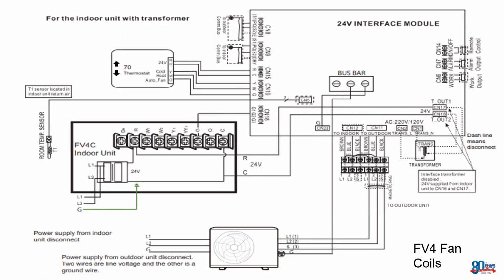Okay, so now what we want to look at is our third-party thermostat. Typically, we see our Ecobee thermostats, which we sell here at Standard Air Lite, but it could be any 5-wire non-heat pump thermostat. Okay, now you have your R and your C, your hot and your common, which is going to feed up to CN15 on the 24-volt interface, which you can see depicted here in the wiring diagram. And then you have your Y, your W, and your G terminal. Of course, they're going to wire to their corresponding terminals. Y obviously is going to be our call for cooling, and W is going to be our call for heating.